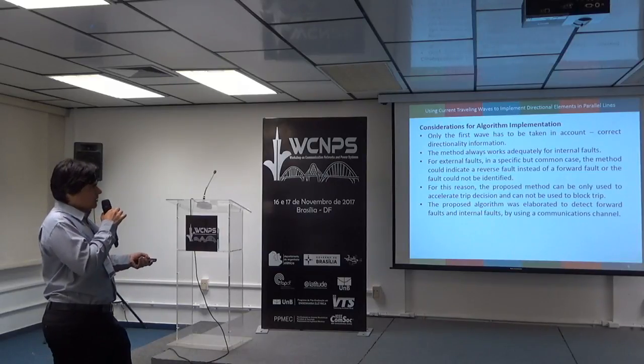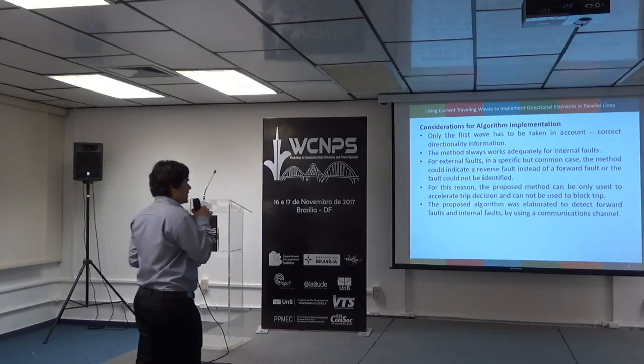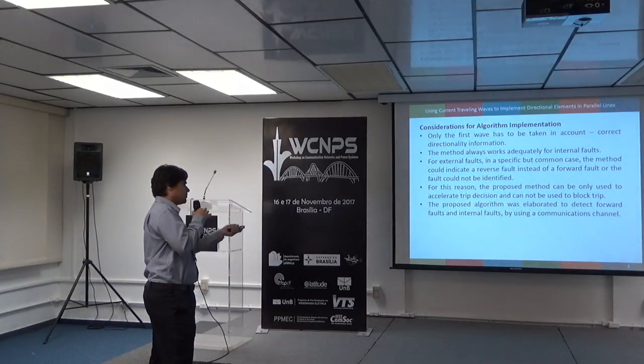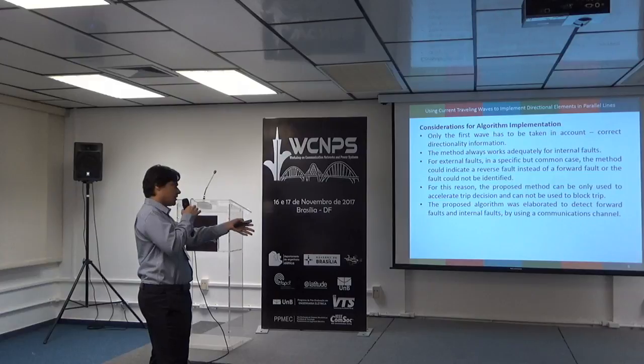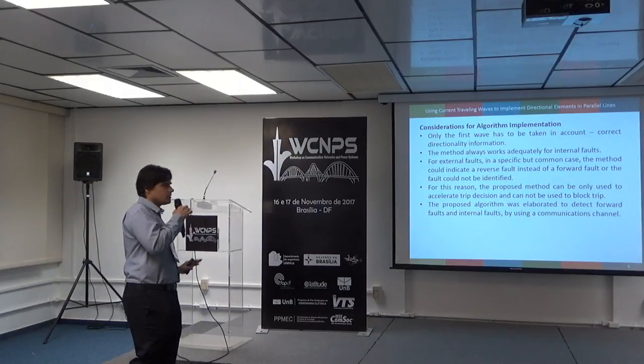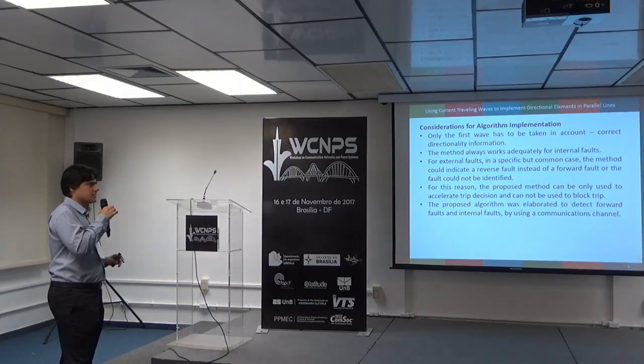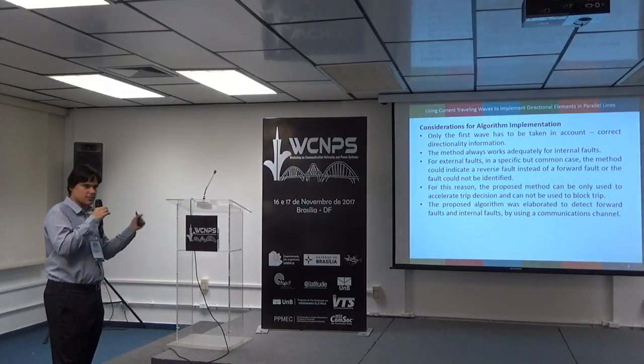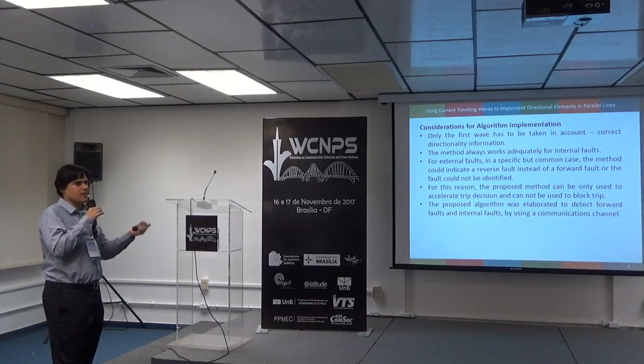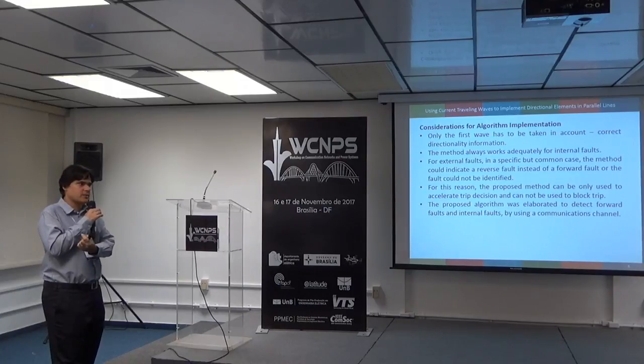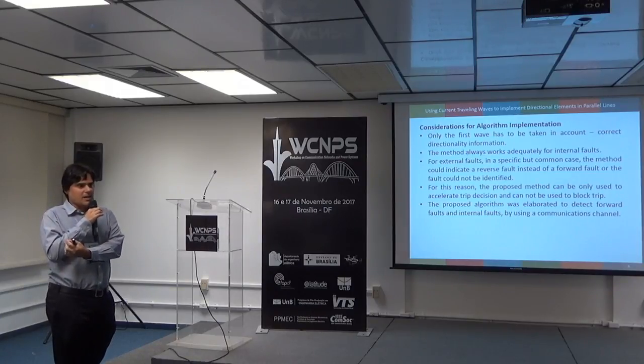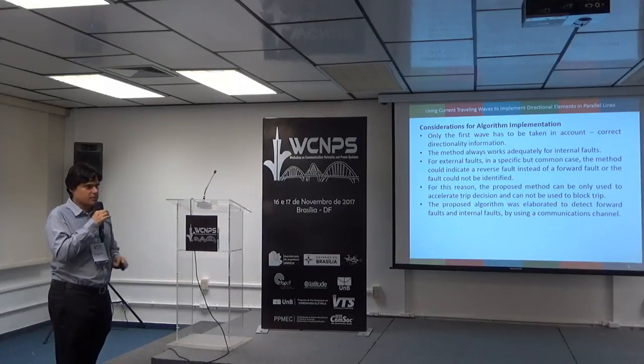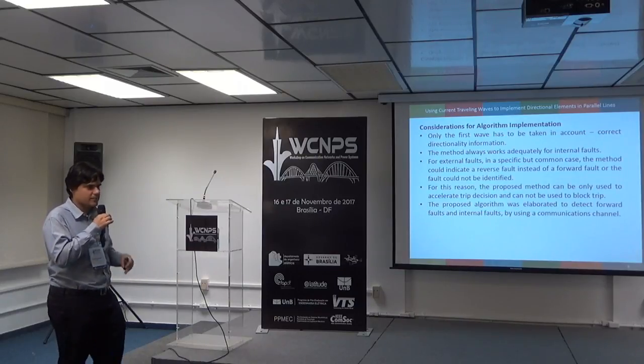The proposed algorithm was elaborated to detect forward faults and internal faults by using a communication channel. If you have a communication channel, we could identify internal faults. And it does not need to be synchronized, because if you have the information that it's a forward fault in one terminal, in the other terminal you have information that it's a forward fault, I need you to send this information. It does not need to have a timestamp for that.